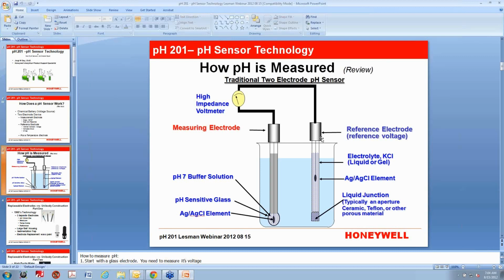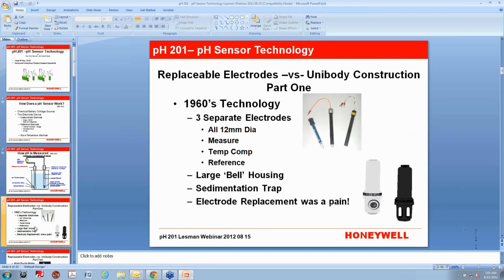So it goes through this high impedance voltmeter, and then it's connected again with a reference on the other side. The reference is, again, a silver chloride wire. It's in an electrolyte of potassium chloride. That's the KCl. And then you have a porous liquid junction, usually ceramic or Teflon or some other porous material. And that allows electrical connection between the two. Okay. So let's go ahead and take a look at the technology of pH sensors.